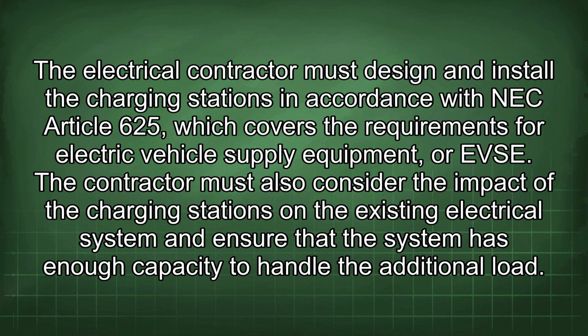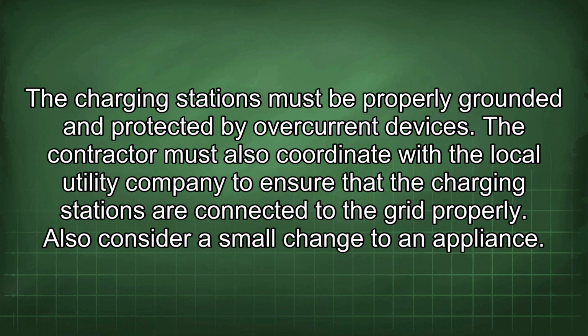The contractor must also consider the impact of the charging stations on the existing electrical system and ensure that the system has enough capacity to handle the additional load. The charging stations must be properly grounded and protected by overcurrent devices. The contractor must also coordinate with the local utility company to ensure that the charging stations are connected to the grid properly. Also consider a small change to an appliance.